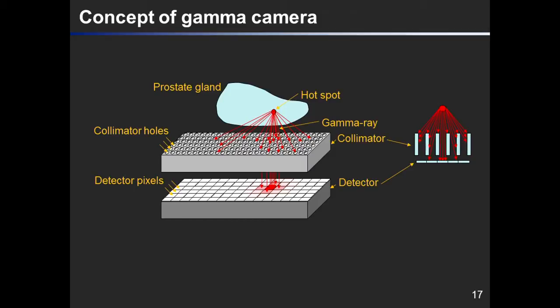For the adjacent holes and pixels, you see the gamma rays go in, and some of them are stopped by the septa between the two holes, but a few of them will go through and be detected by the pixel underneath that. And for the pixels and holes going further away, the gamma rays don't go through anymore. So in this way, the collimator helps us to localize the hotspots into a few pixels right underneath it. Using this technology, we can take an image of the hotspots.